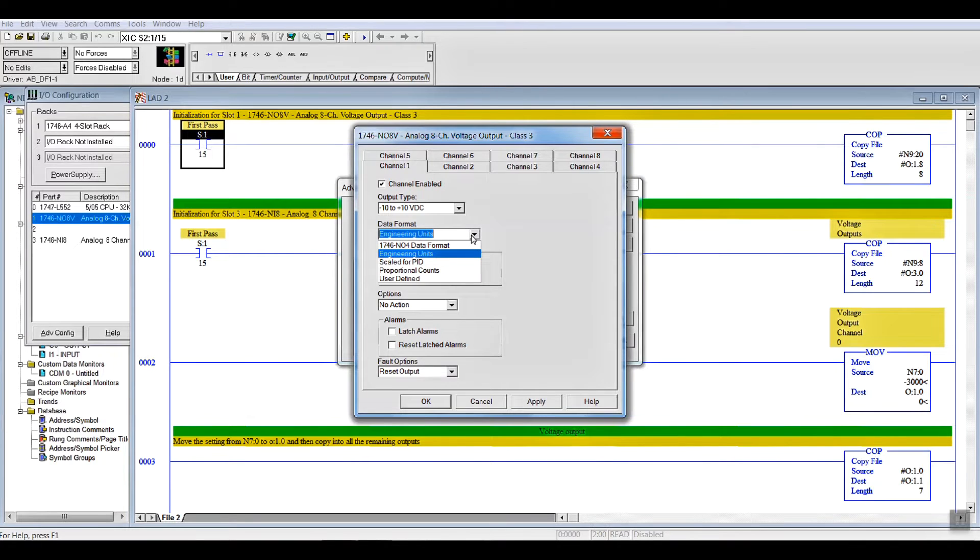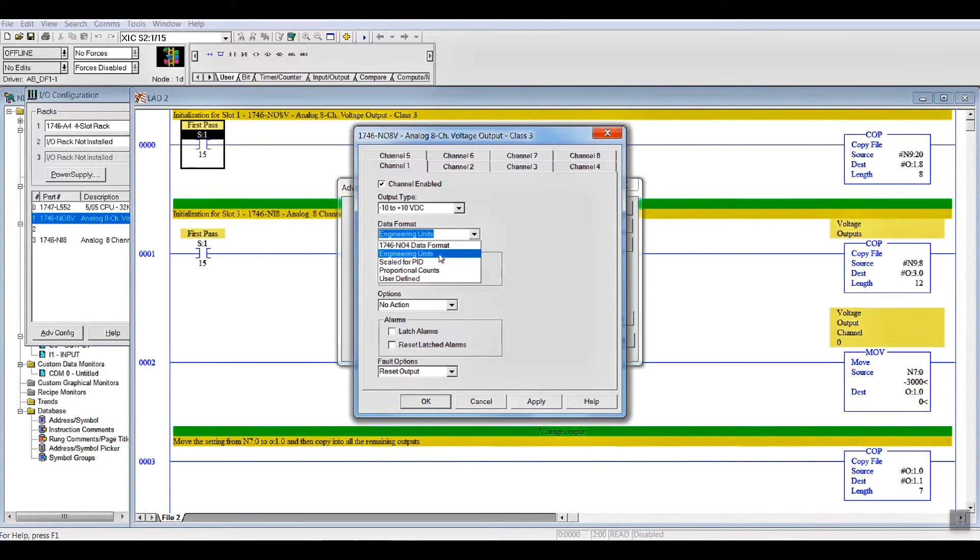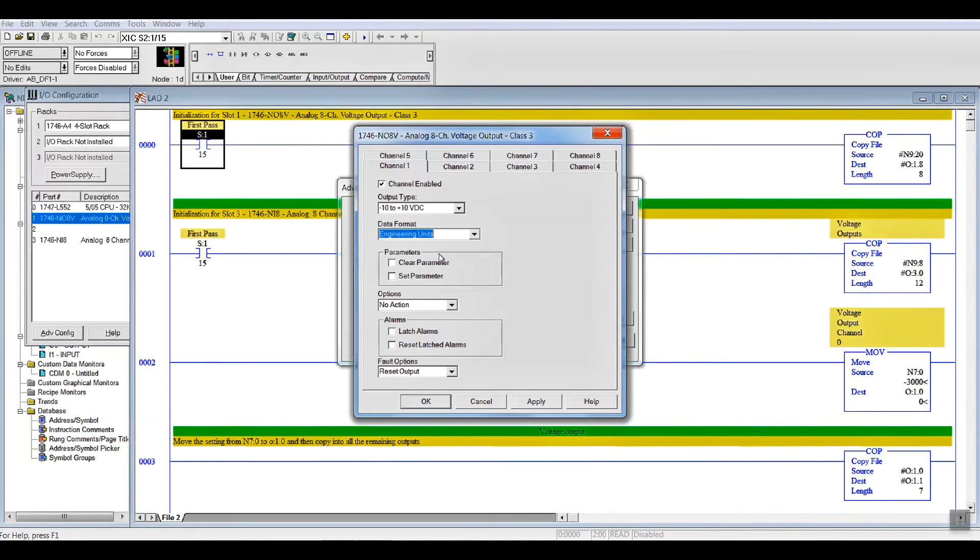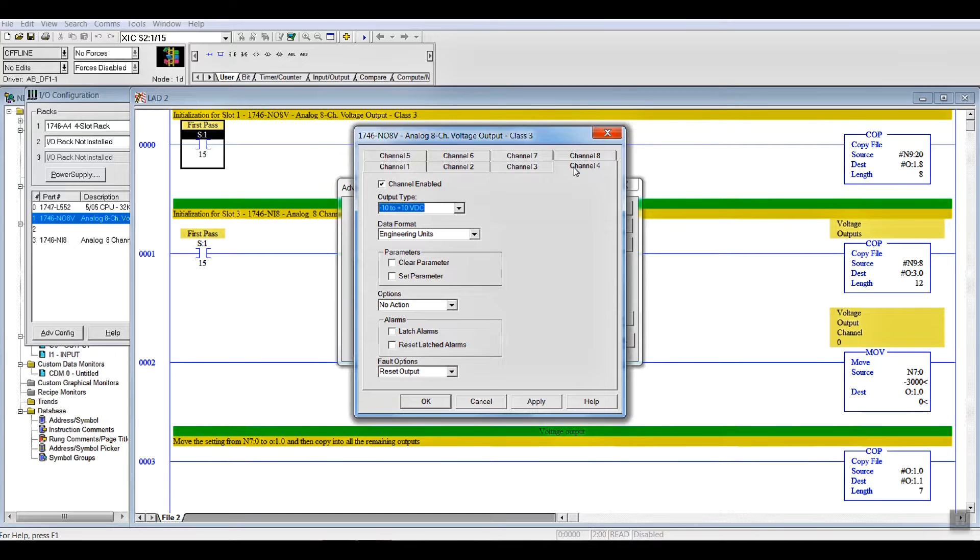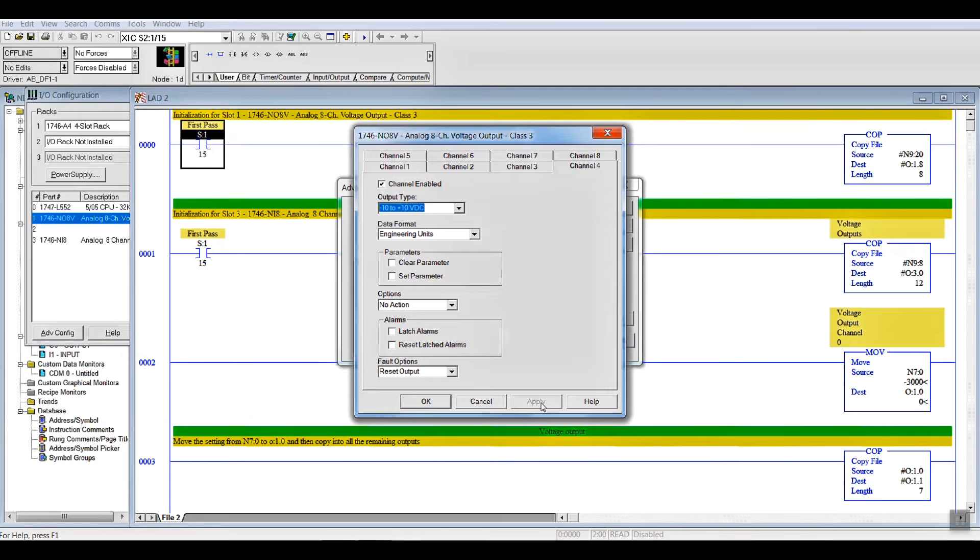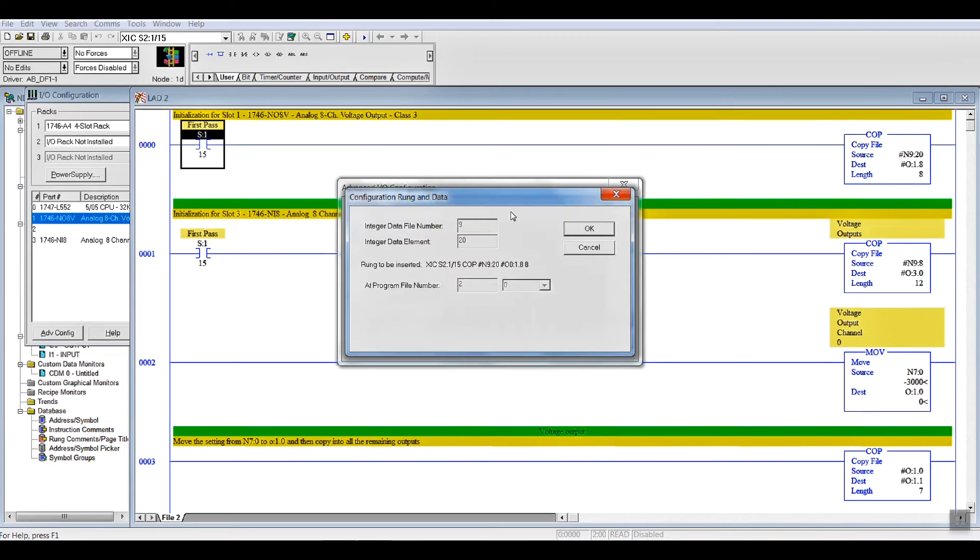On your data format, you've got all of the different formats you want to use. Personally, I find engineering units to be much easier because it's decimal. 0 to 10, plus minus 10. Once you've gone through, you just go through and set up every channel individually. You can't just do one and copy it. You have to do each one individually. You hit Apply. And, as soon as that box grays out, you say OK.